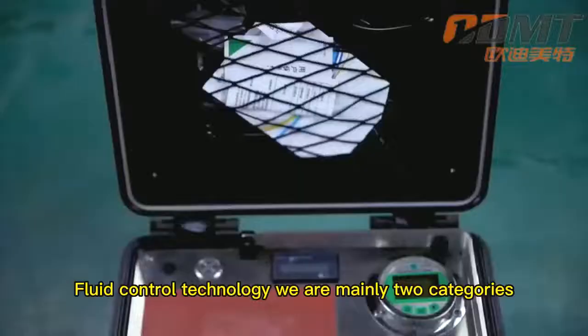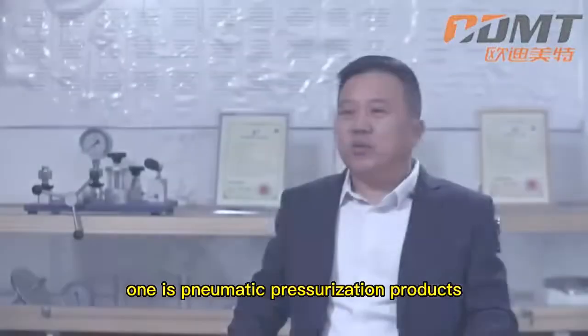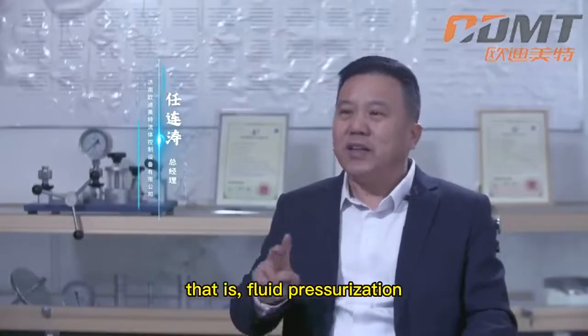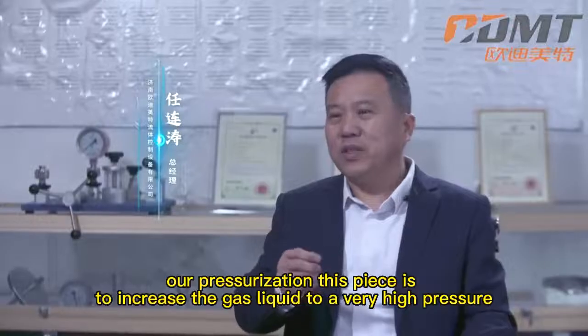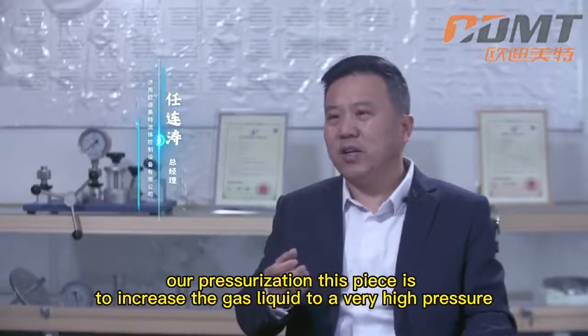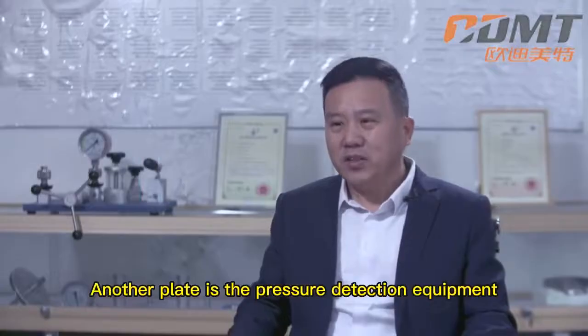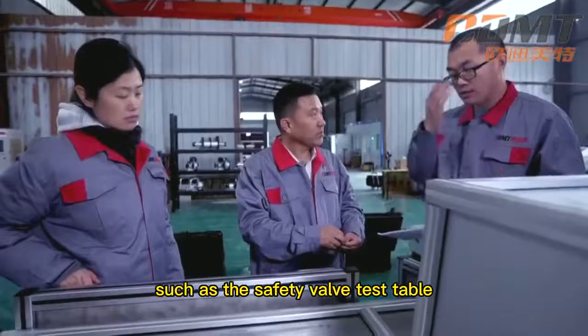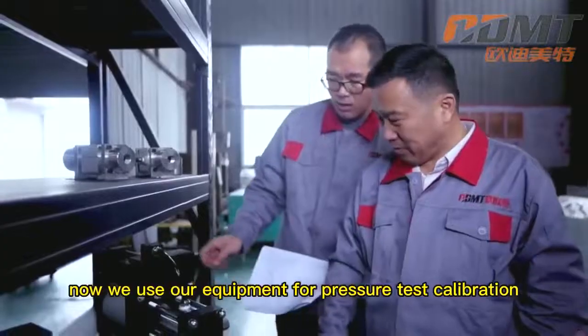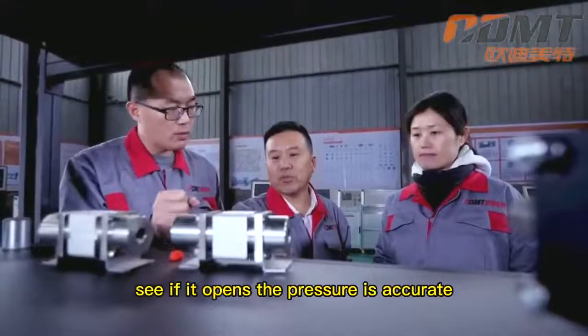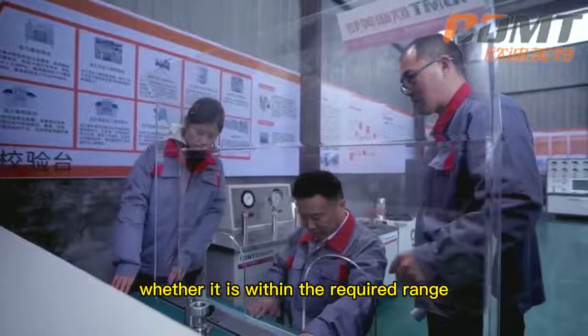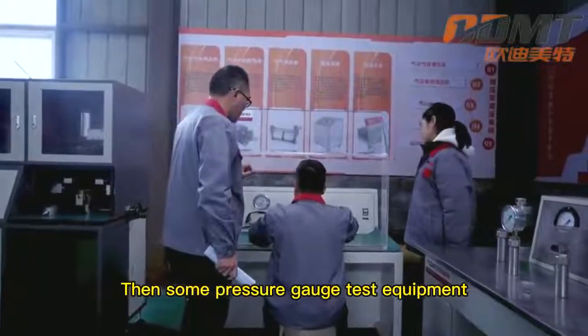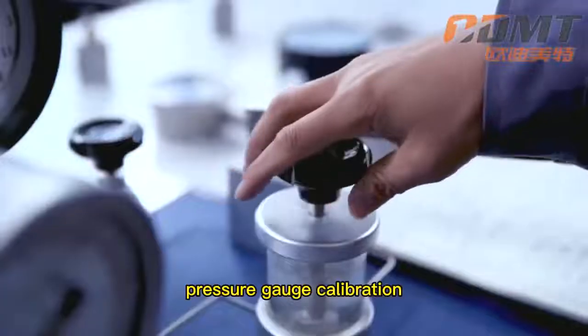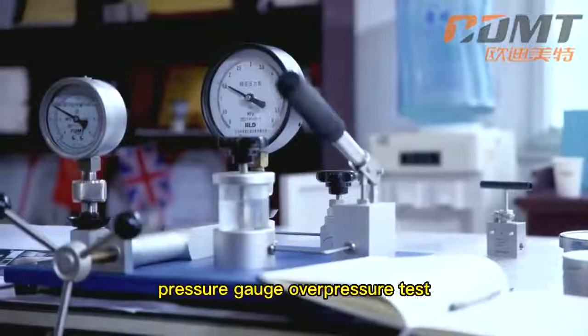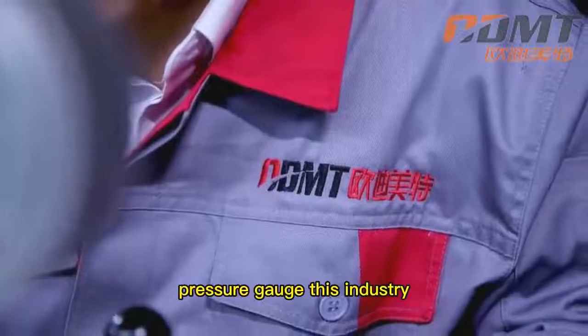In fluid control technology, we mainly focus on two categories. One is pneumatic pressurization products, that is, fluid pressurization - increasing gas or liquid to a very high pressure. The other is pressure detection equipment, such as the safety valve test table. We use our equipment for pressure test calibration, checking if the opening pressure is accurate and within the required range. Then there's pressure gauge test equipment, pressure gauge calibration, pressure gauge overpressure test, and fatigue test for the pressure gauge industry.